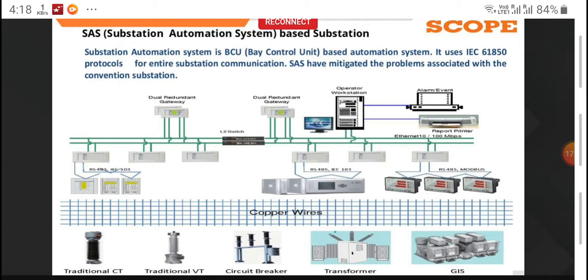These are all still connected with copper cable to the numerical relays. And from the numerical relay upwards, we have done much automation, from the protection relays. From energy meters, voltmeter, ammeter, or MFM, we are still using the Modbus protocol to communicate with our substation automation system.